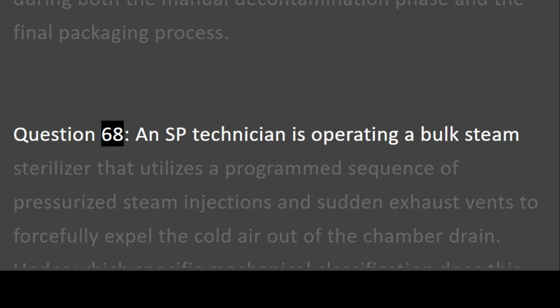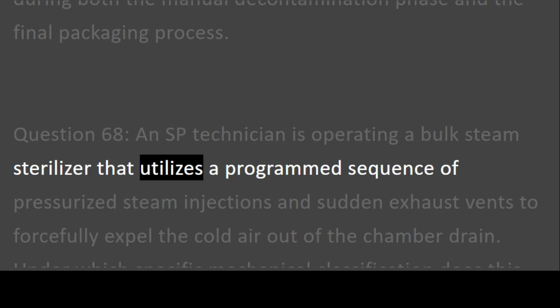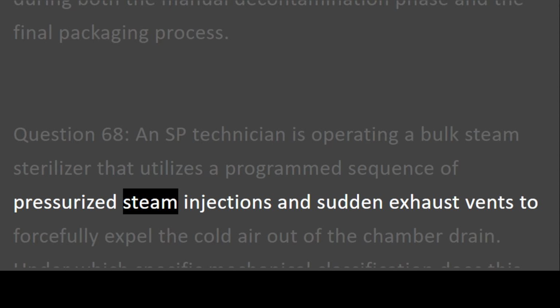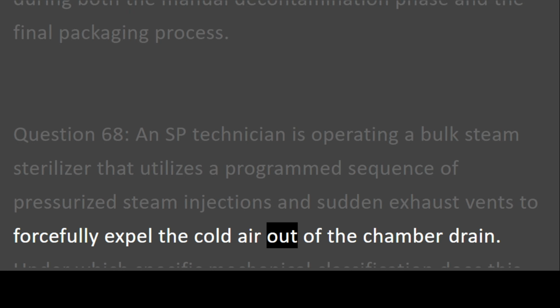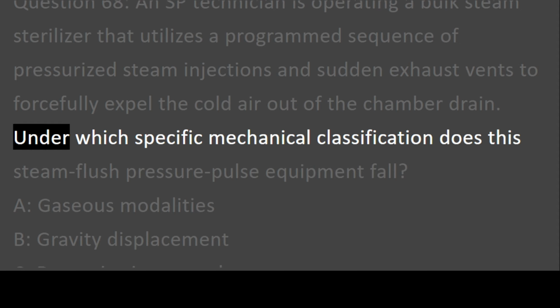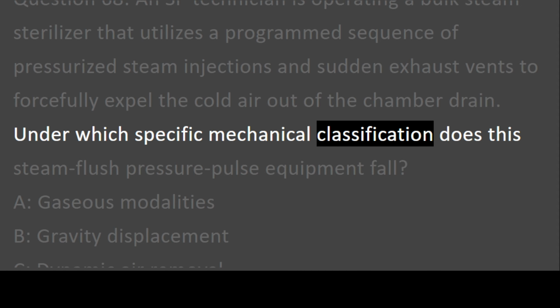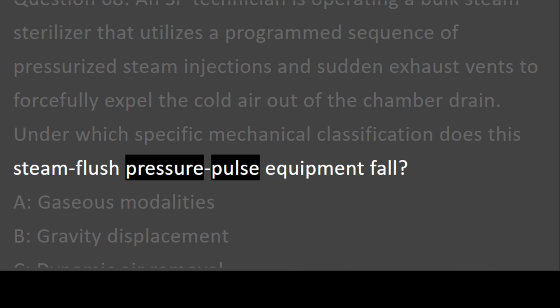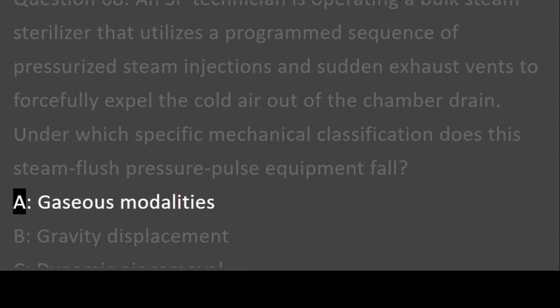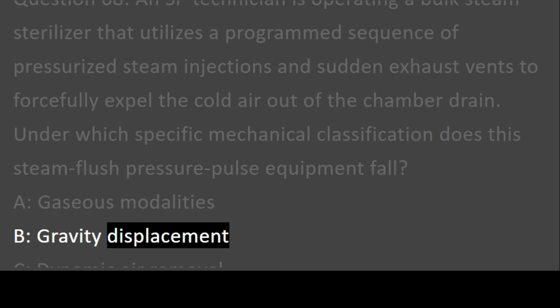Question 68. An SP technician is operating a bulk steam sterilizer that utilizes a programmed sequence of pressurized steam injections and sudden exhaust vents to forcefully expel the cold air out of the chamber drain. Under which specific mechanical classification does this steam flush pressure pulse equipment fall? A. Gaseous modalities. B. Gravity displacement.